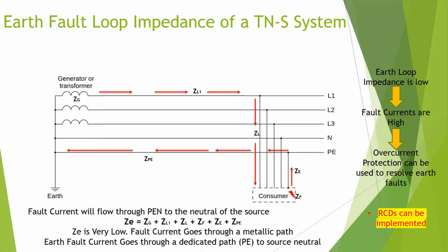So the advantage is earth loop impedance is low and fault currents are high. Overcurrent protection devices can also be used to identify faults. The most important thing is that in these types of systems, it is easier to find faults and clear them. And that is one of the major advantages, because RCDs can be less sensitive. In Sri Lanka, our RCDs are 30 milliamperes, a very sensitive value. 30 milliamperes is a very small current. Here the fault current is very high due to the metallic path, and you can have a higher rated RCD to prevent earth faults. So that is the advantage of the TNS system, and it is very expensive because you have 5 wires instead of 4.